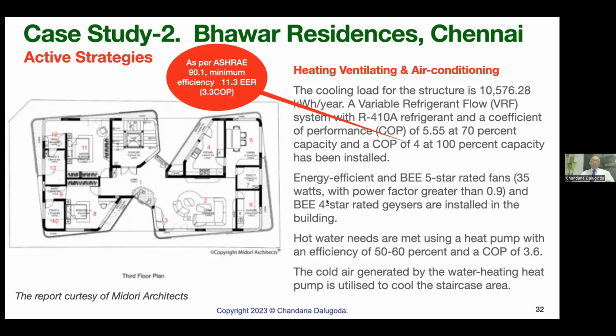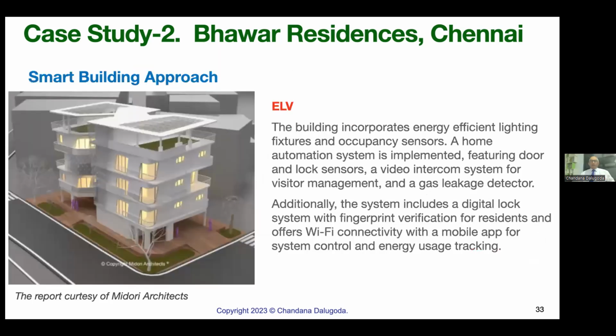But the important thing: for the refrigeration machine, the efficiency is the coefficient of performance; for a heat pump it is always that plus 1. So it is efficient. So we always use heat pumps for water heating. As a byproduct, we have cooled air. Now here they have used that for cooling staircases. ELV: the building incorporates energy efficient lighting fixtures and occupancy sensors. A home automation system is implemented, featuring door and lock sensors, video intercom, and various other things.